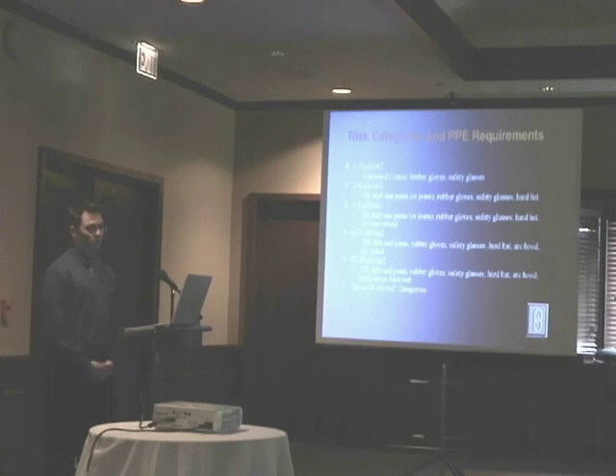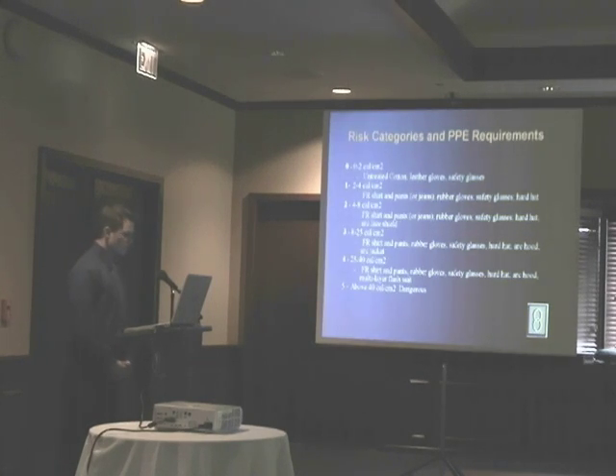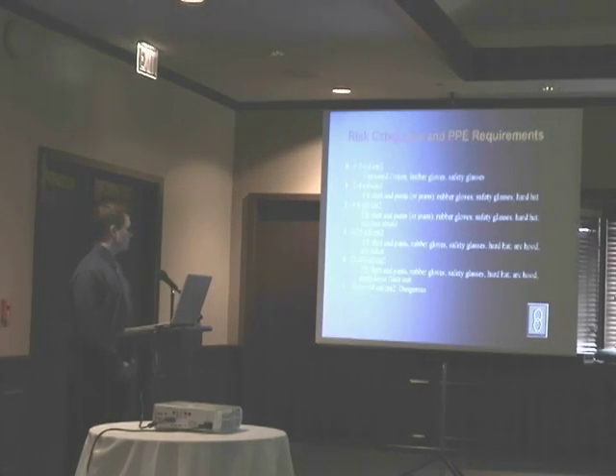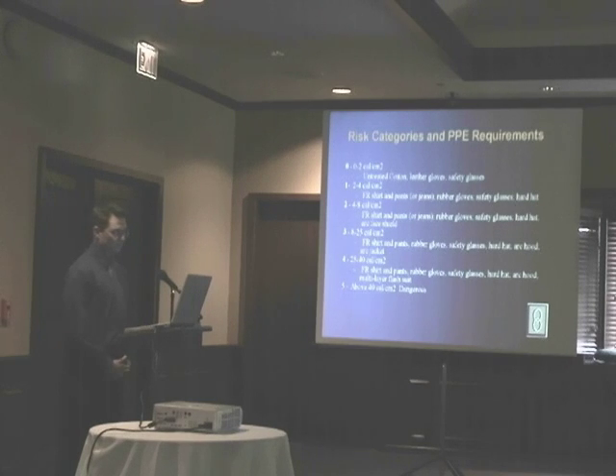And category 4, being the worst that you can actually work on live, is 25 to 40 calories per centimeter squared. You're going to be wearing all the stuff you were wearing before, starting with your FR shirt and pants, rubber gloves, safety glasses, hard hat, arc hood, but you're also going to be wearing a multi-layer flash suit. This suit is going to protect you for up to 40 calories per centimeter squared, and anything over that, this suit is not even good enough. So when you get over that 40 calories per centimeter squared, it's dangerous and you cannot work on it.